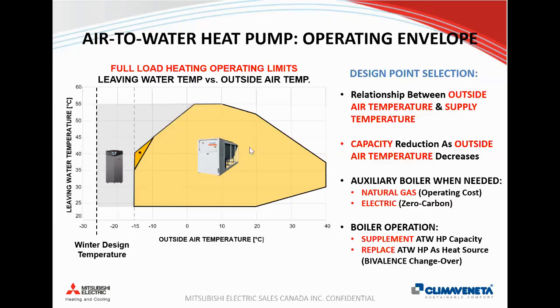And the other limitation that you'd want to watch out for is if you're using a boiler for maybe half the load and the heat pump for the other 50% of the load, you want to make sure that they both have the same supply temperature, because the boiler is not affected by a temperature reduction according to changes in outside air temperature, whereas the heat pump is.